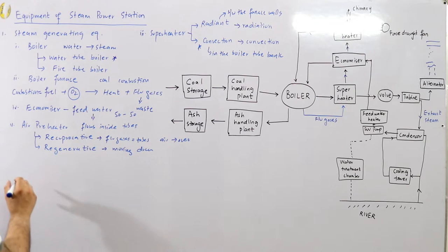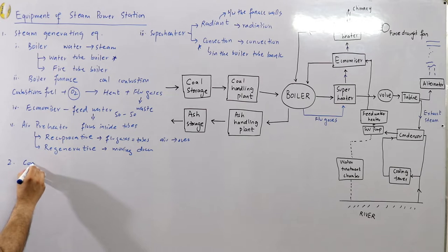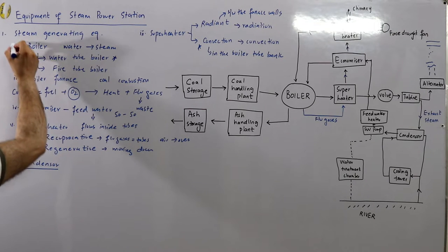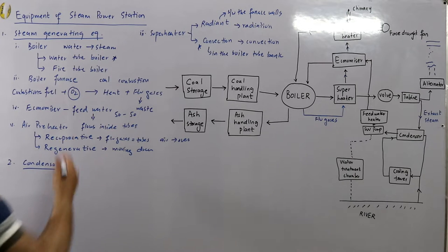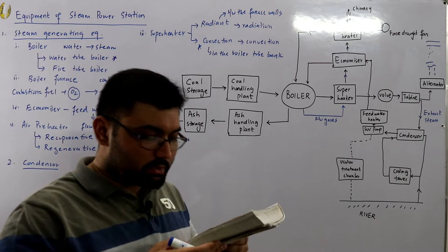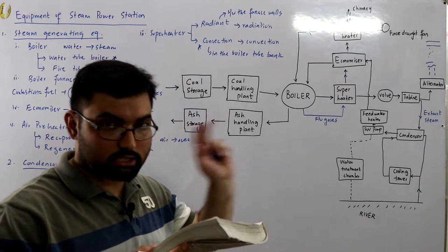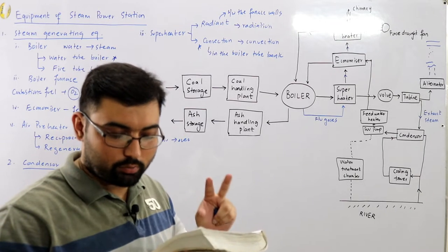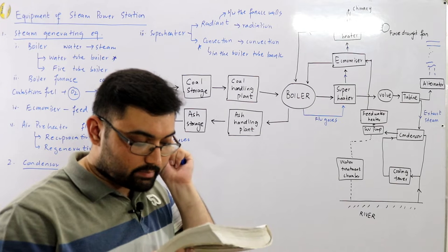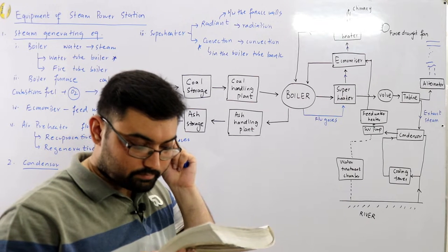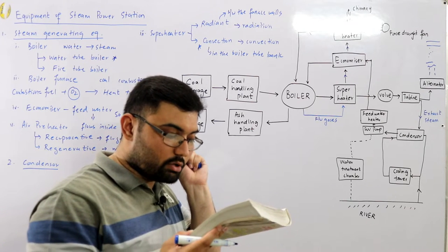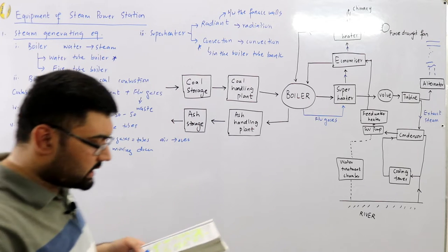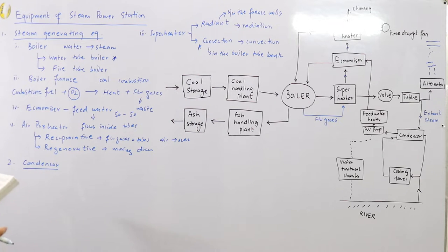The second major category of equipment is the condenser. A condenser is a device which condenses the steam at the exhaust of the turbine. It serves two important functions: firstly, it creates low pressure at the exhaust of the turbine; and secondly, the condensate can be used as feed water. Condensers are of two types: jet condenser and surface condenser.